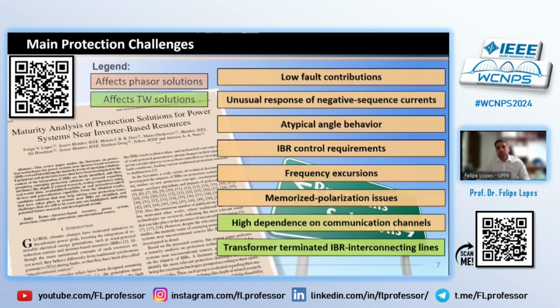And if we consider the context of phasor-based solutions, which are treated here as conventional solutions, and when we consider also the traveling wave-based solutions, most of these problems are expected to affect phasor-based solutions, but only few are expected to affect traveling wave solutions, as you can see in these different colors. The high dependence on communication channels is still a challenge for traveling wave-based solutions. And the terminations and the characteristic of the line terminations also do matter in this case. But these other problems are not very important when we are considering traveling wave solutions.